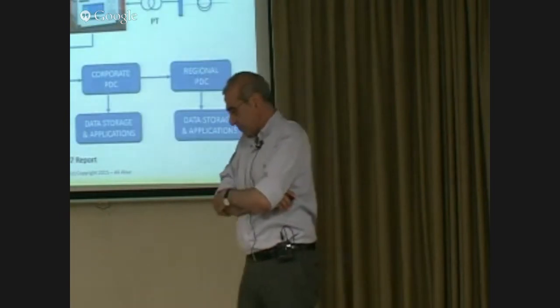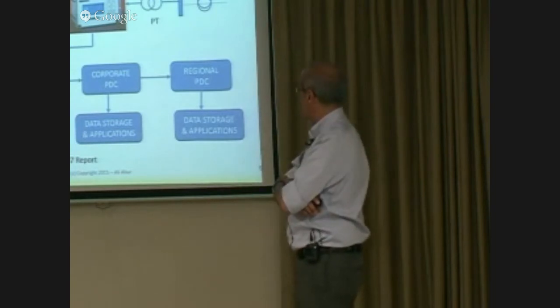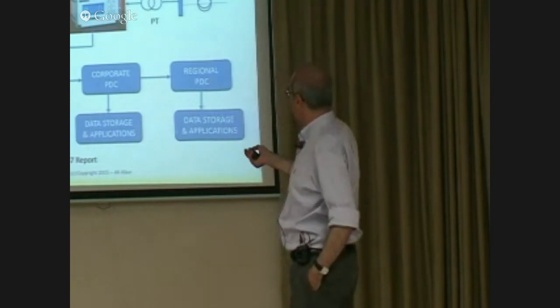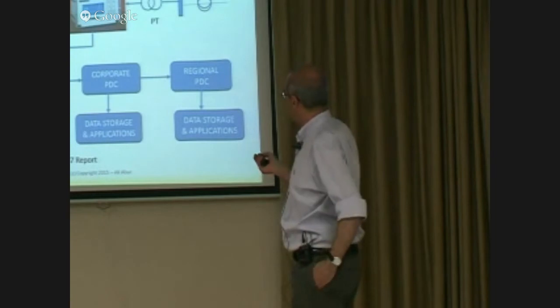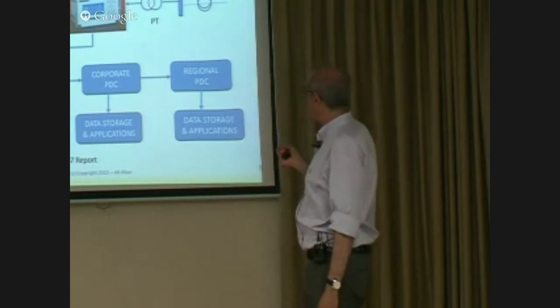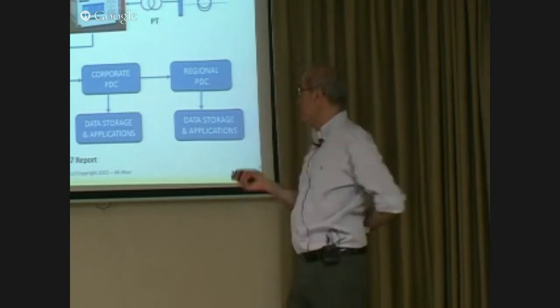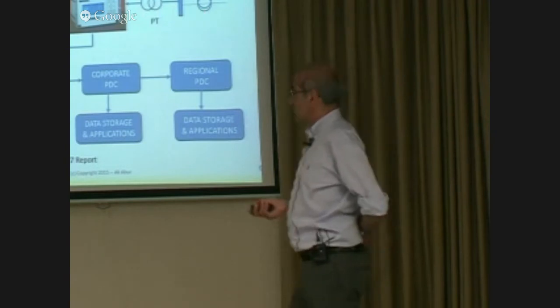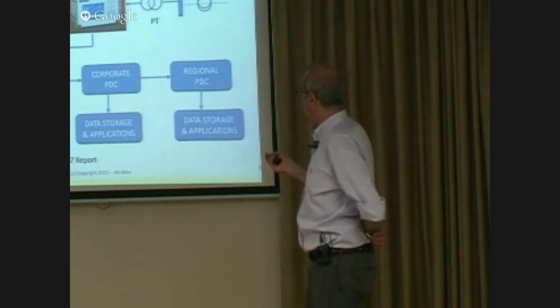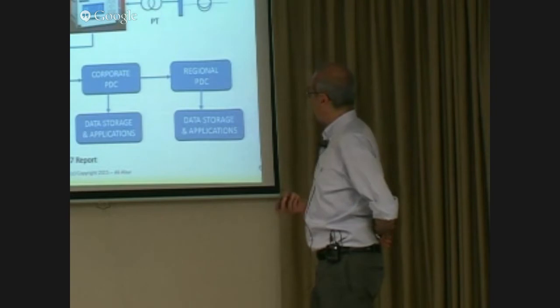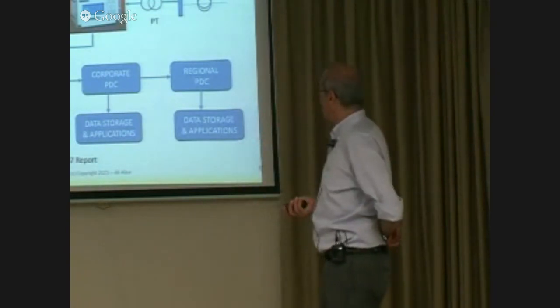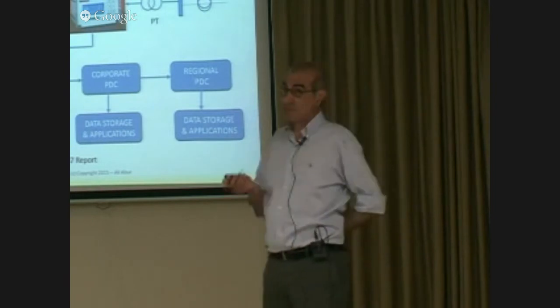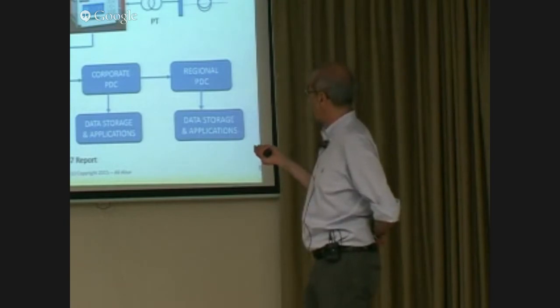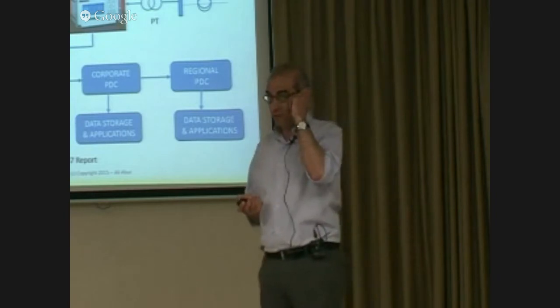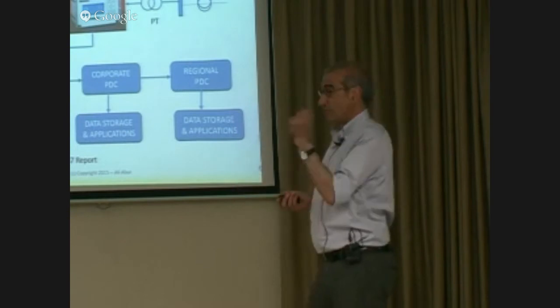So here's the scheme. This is fairly well known, it's just a review. Essentially, here's the box, which is the Phasor measurement unit. The inputs to the box are voltages and currents, coming from the primary power system, and they are collected by the instrument transformers, either a potential transformer or a current transformer. In the secondaries of these instrument transformers, you feed them into the device, and the device samples these voltage or current signals and timestamps them using a clock connected to the GPS through an antenna, so you get a very accurate clock to timestamp these samples.